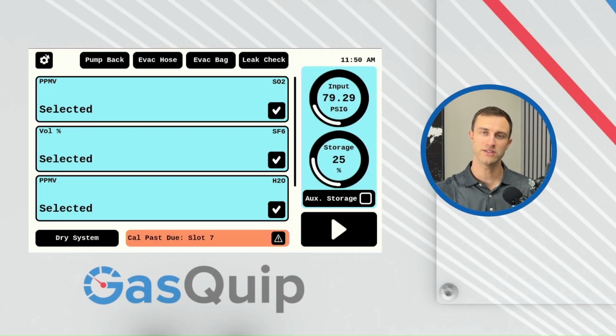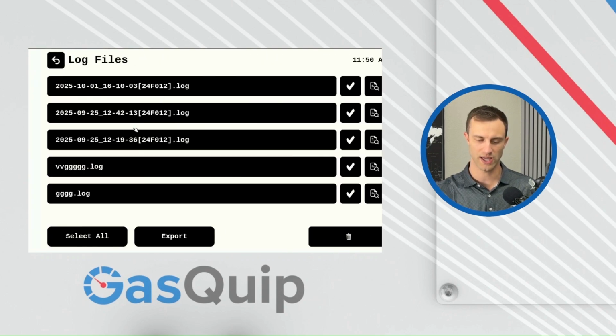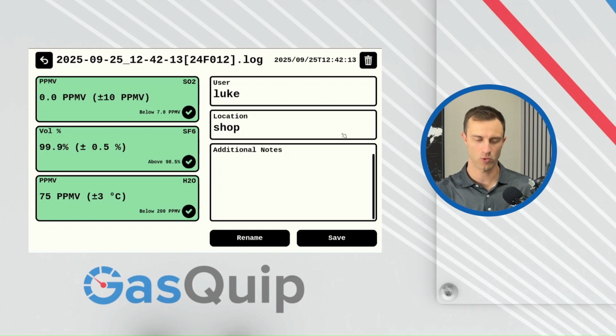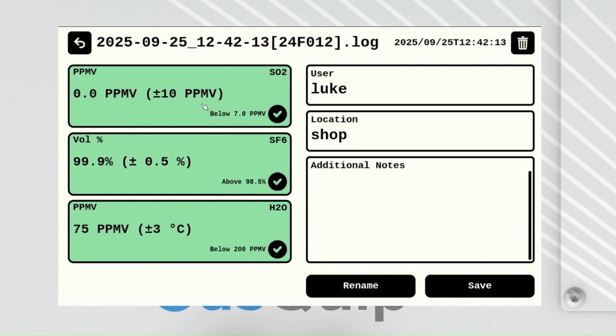Let's take a look at our test limits and test limit settings. And first, before we go into the settings, I want to show you what it looks like to actually have some test limits. So this is a test we ran before. Down here below, we have the individual sensor readouts. These areas down here, let me blow this up for us, where it says below 7 ppmv, that is our set test limit that corresponds to whatever we set in the settings. So for example, for SO2, our readout was 0.0 ppmv, and that is below 7 ppmv. So our whole module area right here turns green, and we get the green check mark.